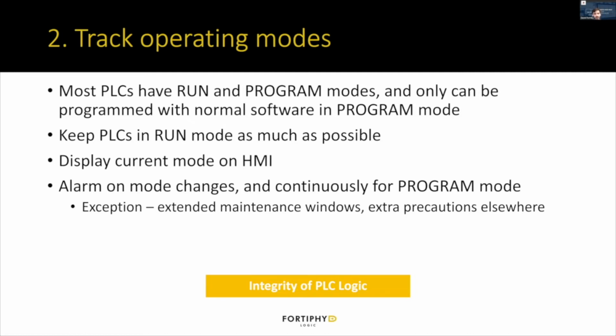It's also really helpful to display the current mode on the HMI and alarm on when that mode changes. And that's really important because depending on the configuration of the PLC, depending on the exact PLC software, once the PLC stops, the values are not being updated anymore on the HMI. And so it may look like it's still running. And so it's really helpful to have that alarm triggered event to raise that alarm when the mode changes.